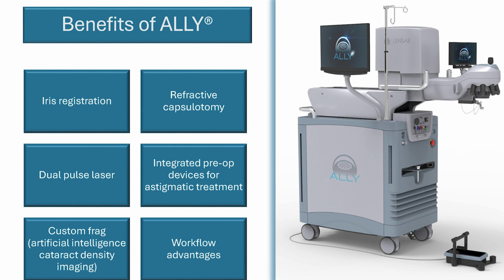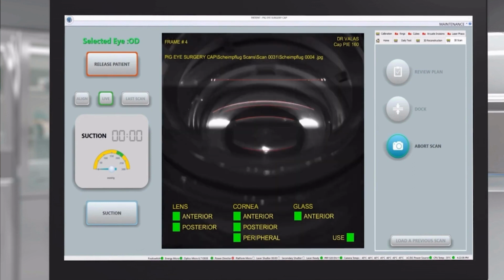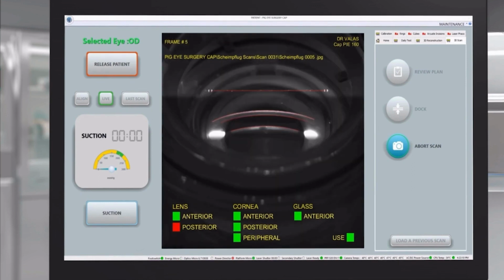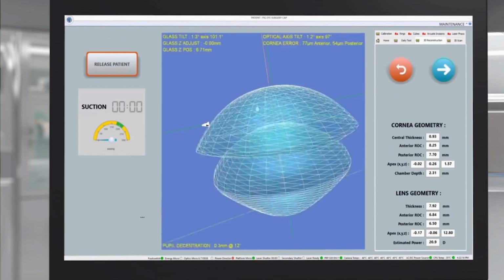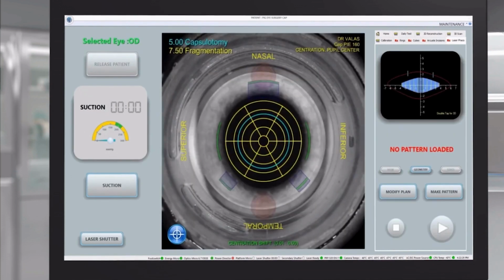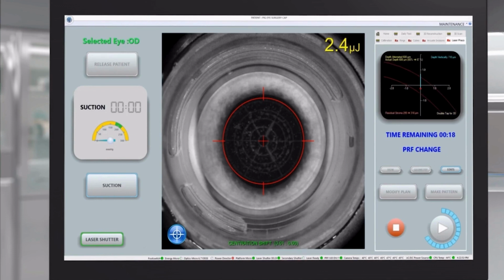So here's a short video. Combination of Scheimpflug imaging, ray tracing, and 3D confocal structured illumination construct a 3D model of the anterior segment that includes the cornea and lens. Using the Ally system, the surgeon will have the opportunity to center the capsulorhexis on the pupil center or the anatomical lenticular axis. Cataract density imaging uniquely identifies nuclear morphology and categorizes density from 1 to 5. The fragmentation pattern and phacoparameters are then adapted according to density to reduce the combined energy delivered to the eye for optimal lens removal with the potential for faster visual recovery.